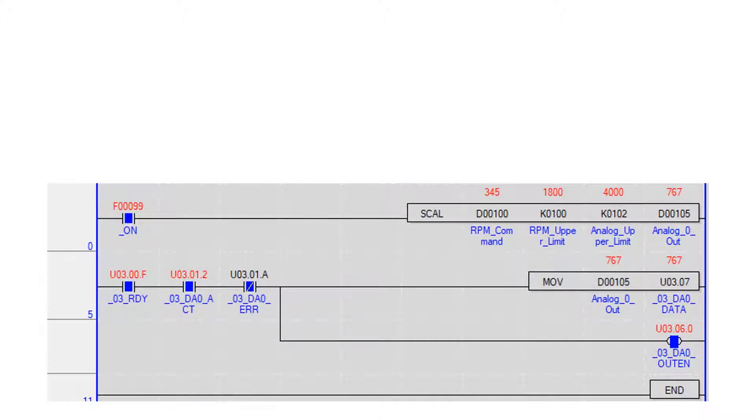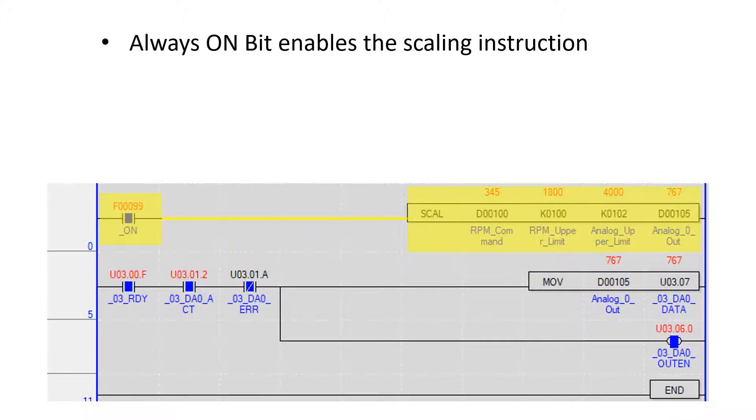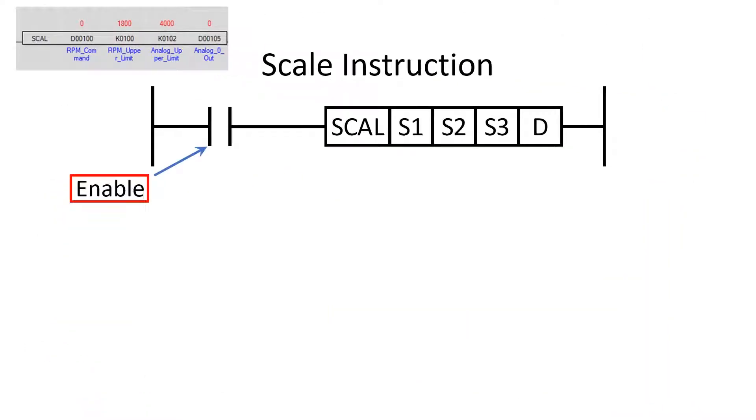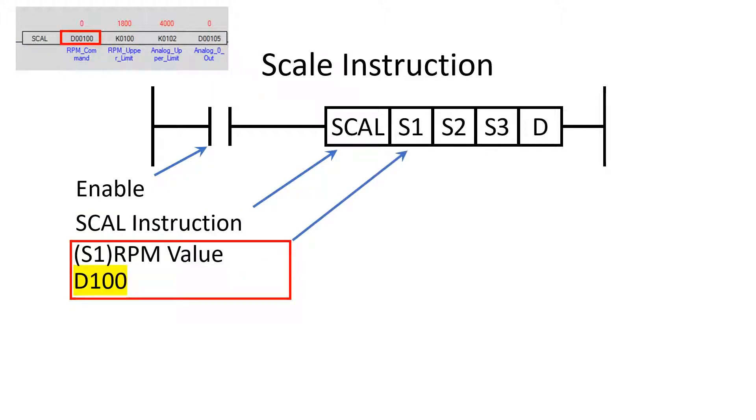In this example, the always on bit enables the scaling instruction. An enable condition is required when using the scale instruction. This program uses the SCAL instruction. Operand S1 stores the speed command data. In this program it is memory location D100. The PLC received this data from the operator interface.